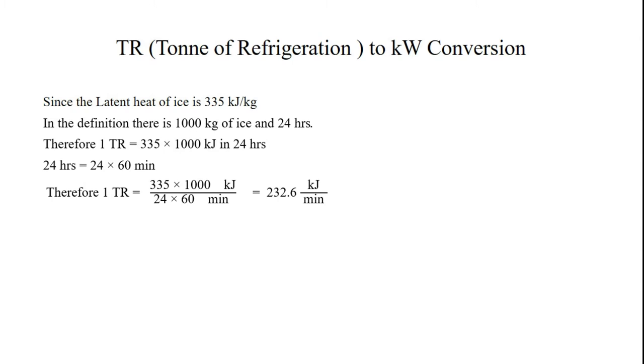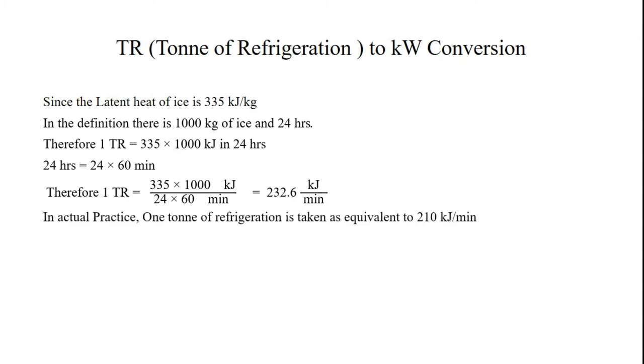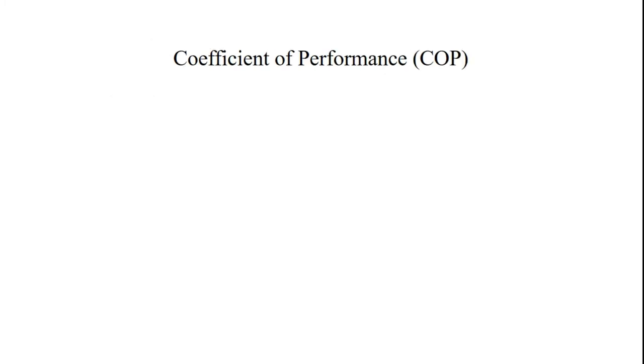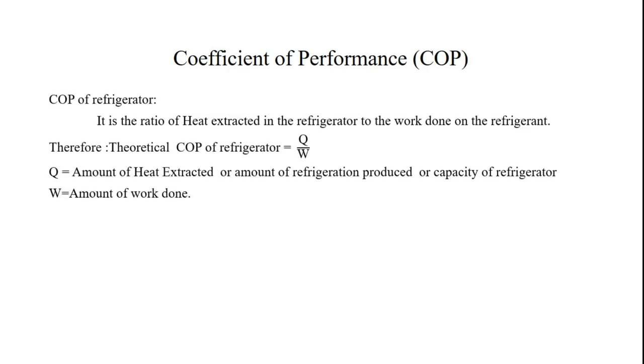This equals 232.6 kJ/min. In actual practice, 1 ton of refrigeration is taken as equivalent to 210 kJ/min. To convert 1 TR to kilowatt, we divide 210 by 60 to get kJ per second (i.e., kilowatt). Therefore, 1 TR = 210 kJ/min = 3.5 kW.